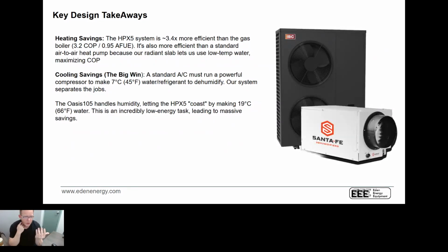The key side effects: if you look at what it is to heat a home using the water temperatures we use currently for heating, we're maintaining a slab at 85 degrees. With an air-to-water heat pump, we can maintain a COP in excess of 3. And that's the beauty of an air-to-water heat pump: we're choosing our emitter. Now, if I put an air-to-water heat pump in and I use a large coil that needs 140-degree water, well, you're not going to have a COP of 3. We have the option to choose the emitters.